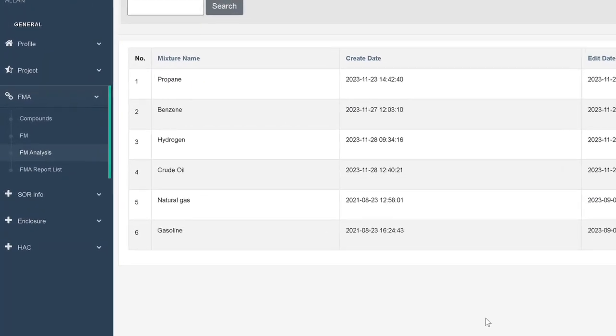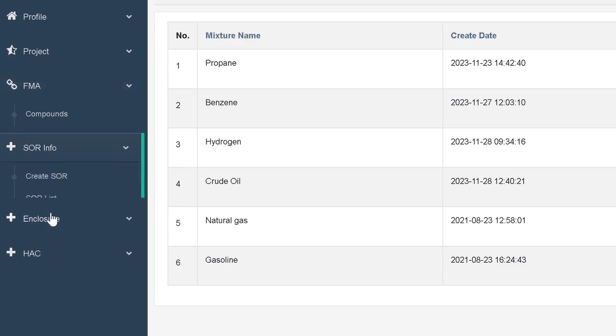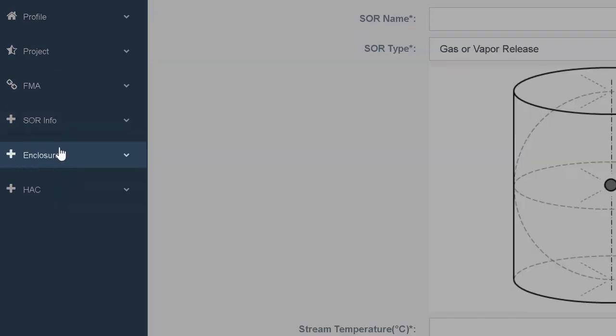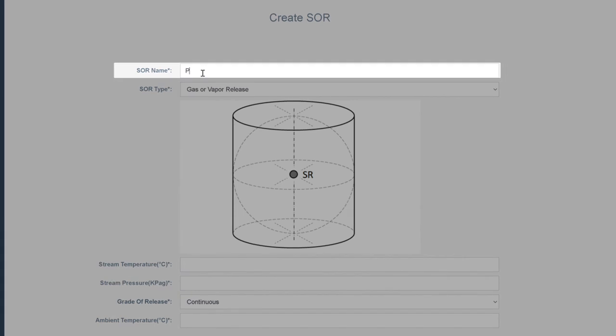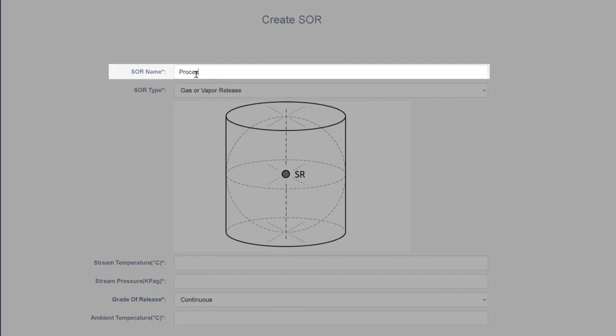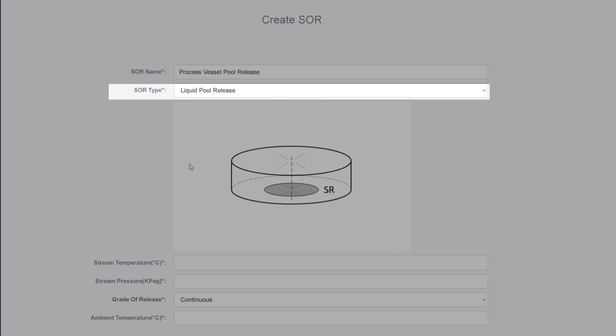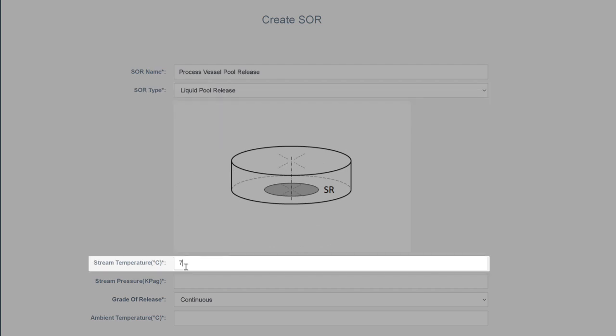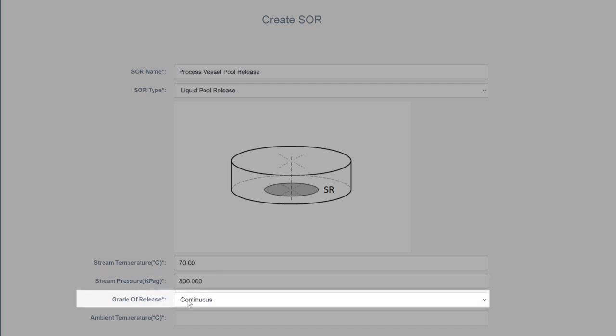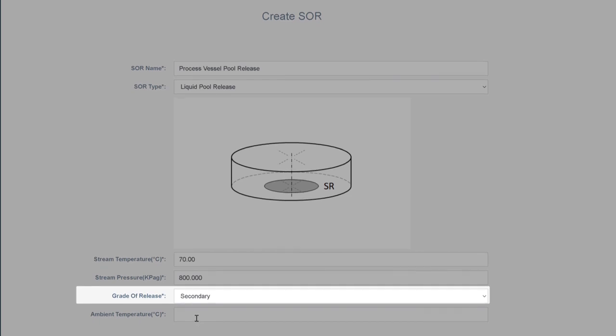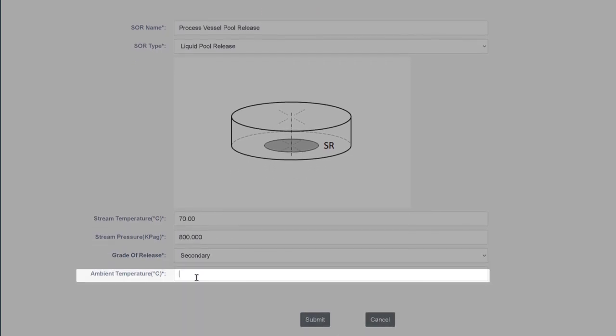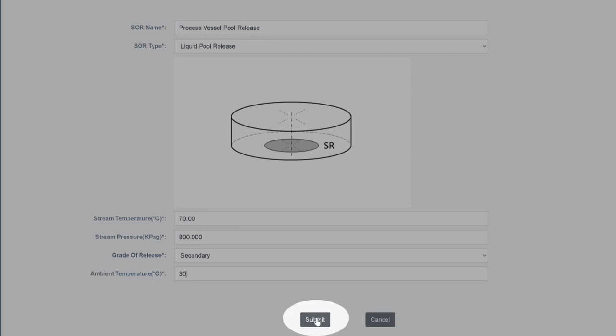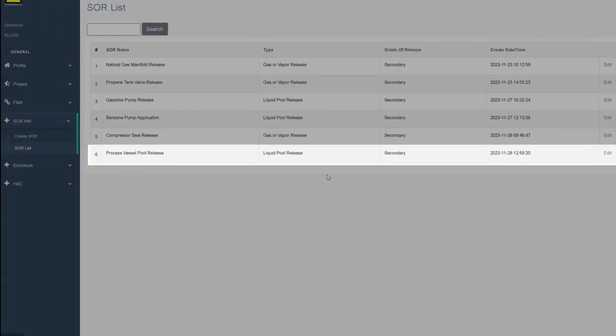Now, we need to create the source of release. We will name this SOR process vessel pool release. The pool release would likely result from a flange, valve, or sample drain point on the vessel. Our stream temperature is 70 degrees Celsius. The stream pressure is 800 kilopascals. The grade of release will be secondary as we do not expect a release in normal operation. The ambient temperature is 30 degrees Celsius. Click submit and the SOR will appear in the SOR list.